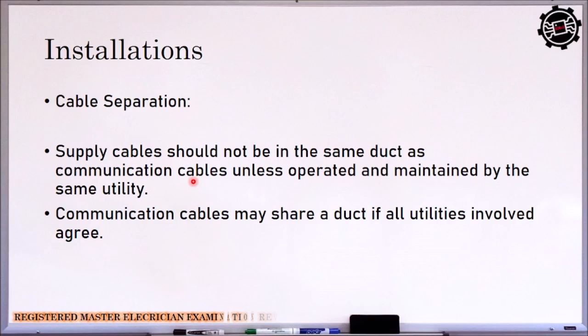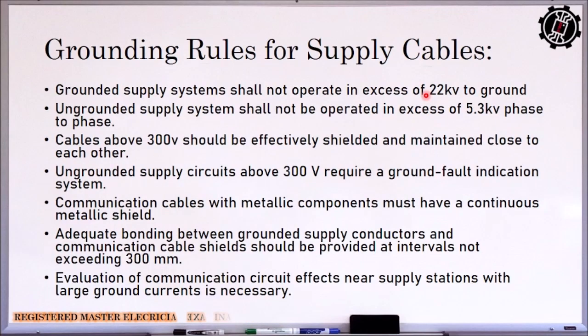Then communication supply cables buried in random separation can be treated as one system for considering separation from underground structures or facilities. Then deliberate separation, supply and communication cables may be buried together if the two parties agree. The other company will agree that they will have the same routing. The grounding rules for supply cables. So a grounded supply system shall not operate in excess of 22 kV to ground. Then an ungrounded supply system shall not be operated in excess of 5.3 kilovolts phase to phase.